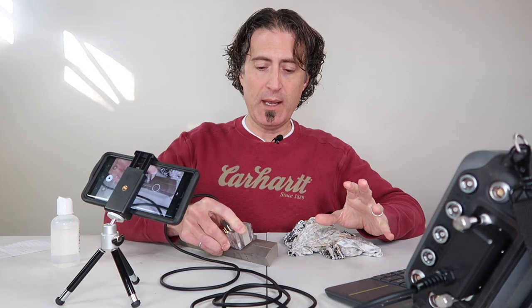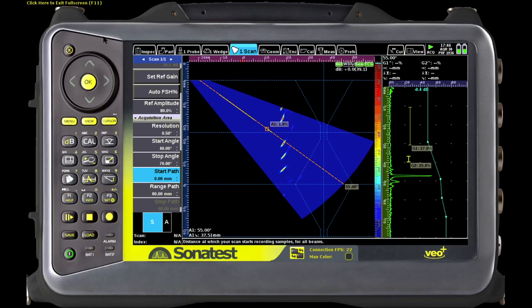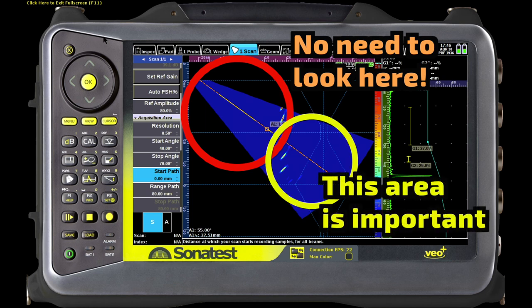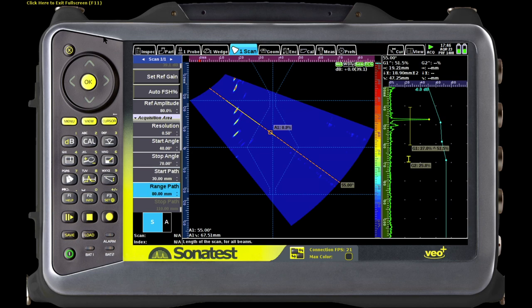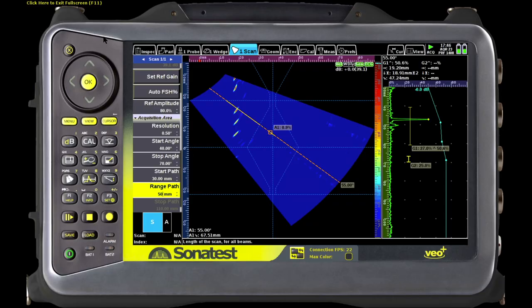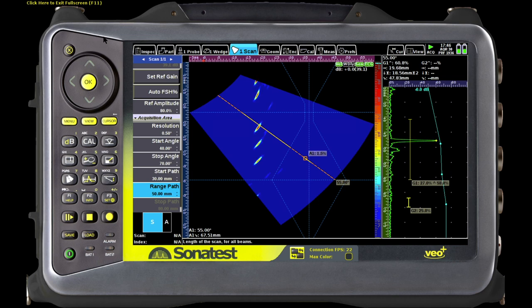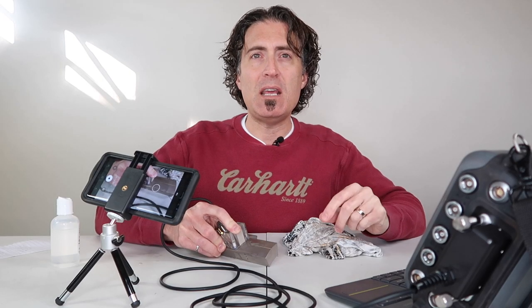Now we've finished our TCG and there's one more thing we can do. We can take our start and range path and change those a little bit. This doesn't really have anything to do with the TCG, but it's a good idea to keep your file size at a reasonable level. On the S-scan right now you can see it's starting at the entry surface at zero — there's really no point in doing that. We're not trying to find anything right under the surface where the probe is sitting. So we're going to take our start path and increase it so it starts closer to where we're interested, and then reduce the range path. I put 30 on the start path so I'm going to take 30 off at the end of the range. It almost looks like it's zoomed in — it will keep the file size down and makes it easier to see things on the fly.